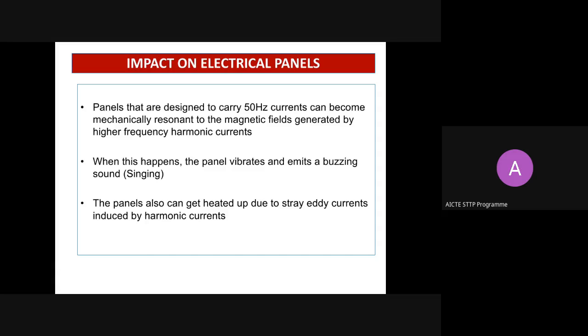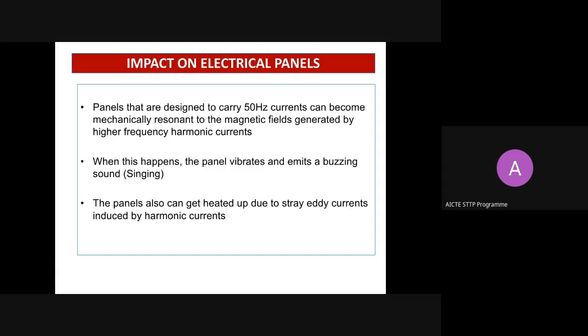So there is a problem on the transformer side, a problem on the neutral conductor side, and then electric panels. Electric panels are normally designed to carry 50 Hz currents. But because of higher frequency harmonic current, the panel boxes become resonant. When this happens, the panel vibrates and emits a buzzing. If you enter the control room in an industrial area, or a substation located at an industrial complex, you will hear a buzzing noise. Why does the panel vibrate? All because of harmonics present in the industrial system. The panels also get heated up due to stray and eddy currents induced by harmonic currents. These are some of the impacts on the electrical equipment in the system because of harmonics.